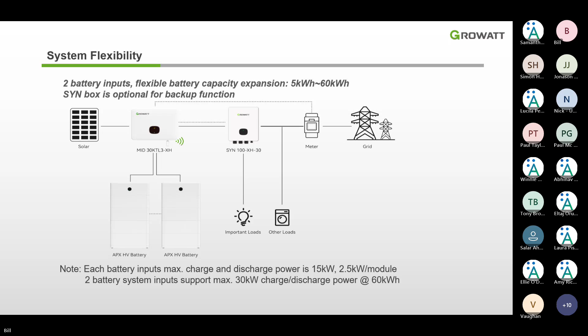And since it is a three-phase system, it comes with an unbalanced control function. That means, for example, if we set the export limiting to around 3 kilowatt, each phase technically should be 1 kilowatt. But when one of the phases requires 1 kilowatt for some loads, for example, here you can see phase one will generate 2 kilowatt, and each of the other phases is 1 kilowatt. That means 100% unbalanced control. One kilowatt goes to your load, and the rest, 3 kilowatt, will be exported to your grid.